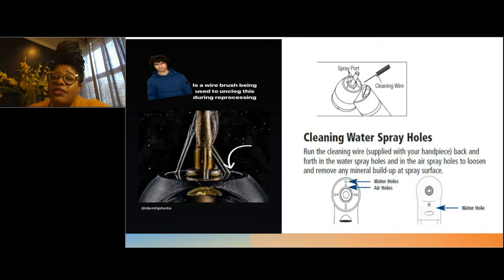So I want you to take a look at these next clips. They're actual clips of placing that little tiny wire brush into these ports that are being displayed here and in the excerpt of this IFU. It was not an easy task. As the wire brush was being placed into those holes, it would jump back because there was so much mineral buildup and clogging within these portholes. And if you look closely, these portholes in this handpiece had 8 holes, and the inner ones were smaller than the outer ones. So the reprocessing of this handpiece does not happen as fast, because it requires so much attention to detail.